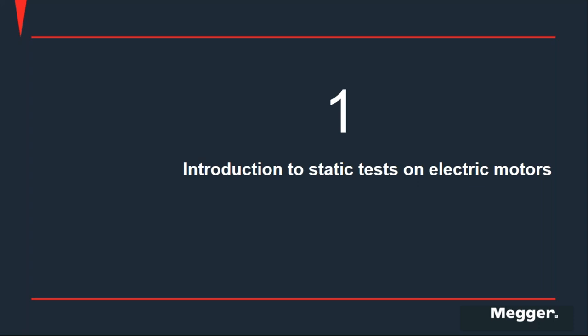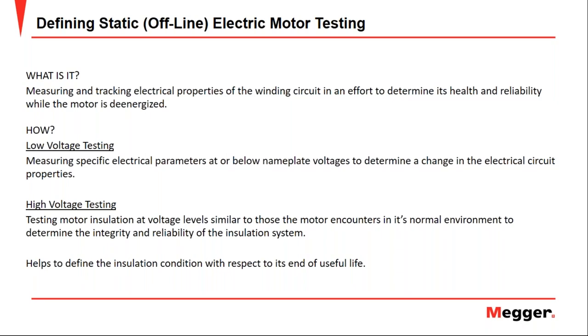Let's see then what the static tests are and how they are performed. Let's start by giving a concept to the static tests and knowing what they are. What do they tell me? These tests are carried out to establish the state of the motor insulation system when the motor is de-energized and, if possible, disconnected. This test must be done in the motor junction box. However, we know this is not always possible, so in those cases we have to do it from the MCC.